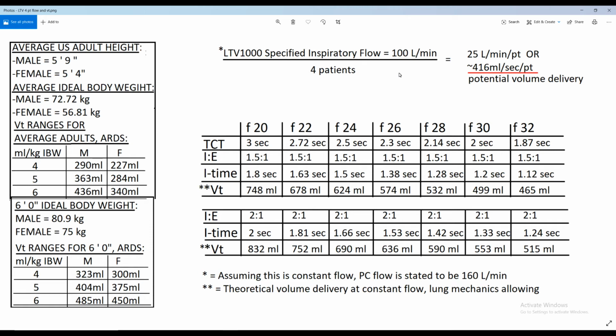So what does that work out to as far as mLs per second? 25 liters per minute, that's the same as 25,000 mLs per minute, which is the same as approximately 416 mLs per second per patient of potential volume delivery. So that might not seem acceptable. Well, I know normally we have inspiratory times around a second for most of our adults, and 416 isn't going to be enough except for my tiniest patients, so that's definitely not going to work.